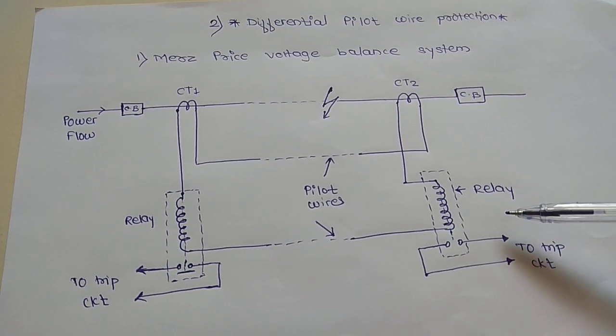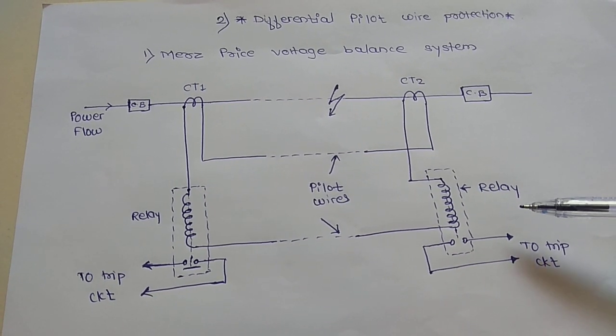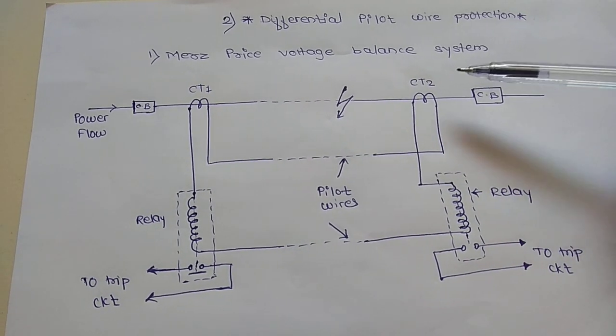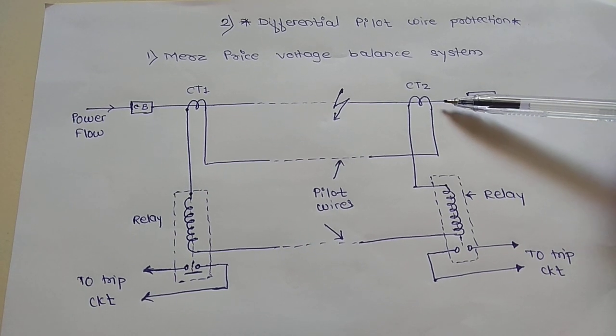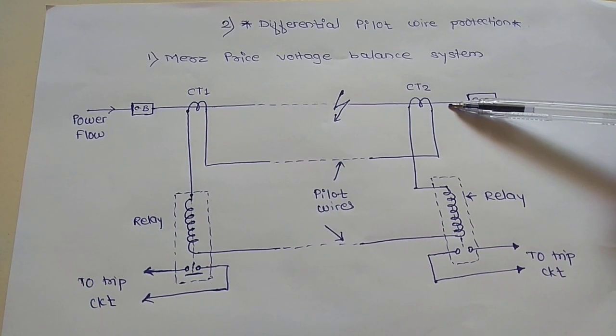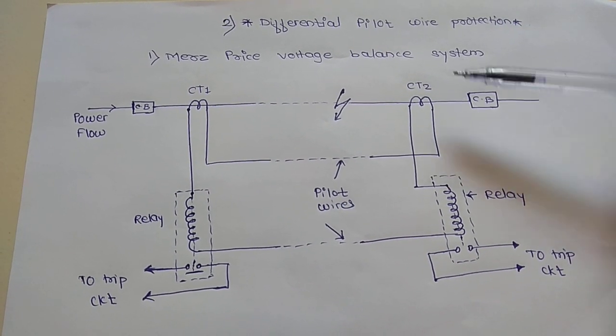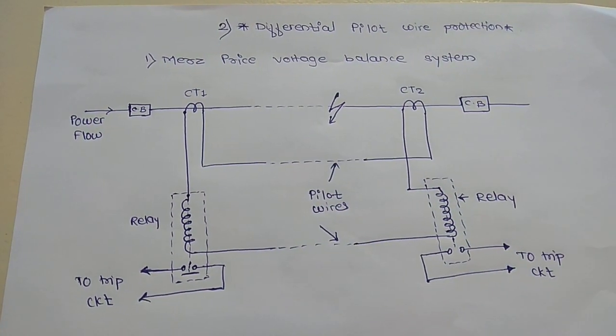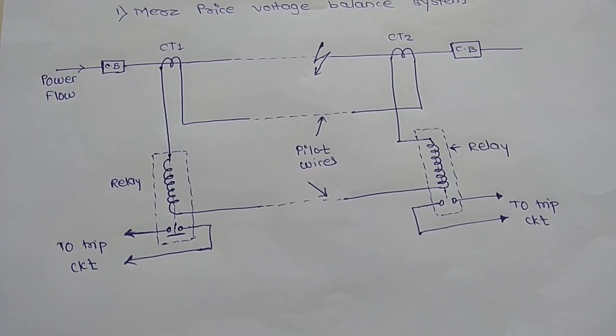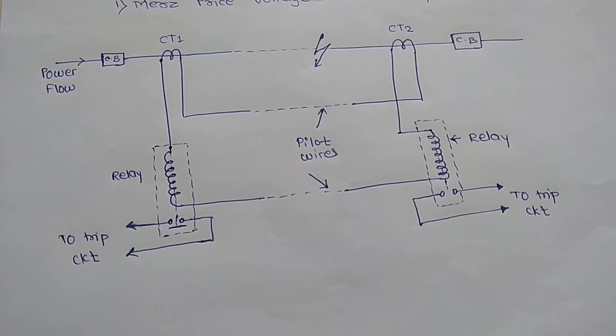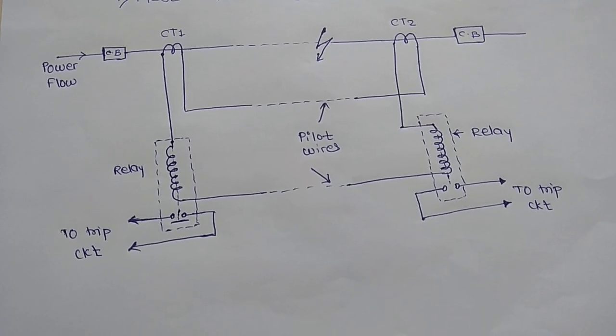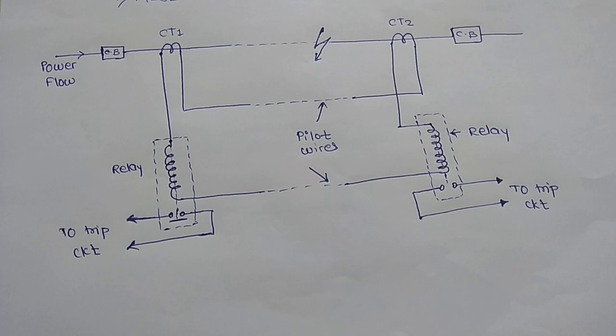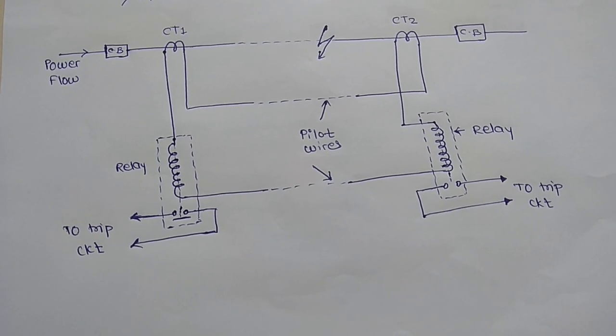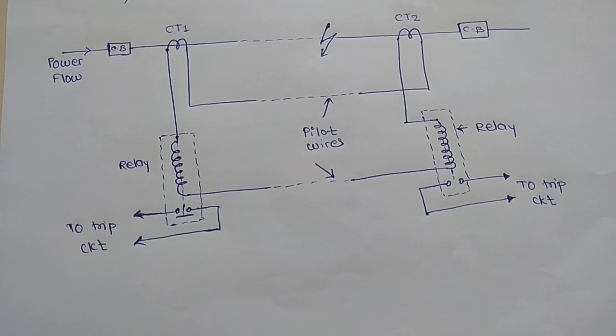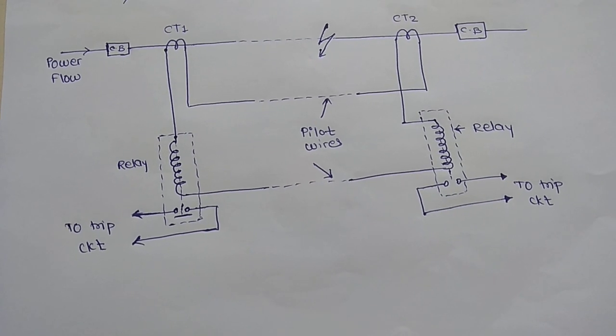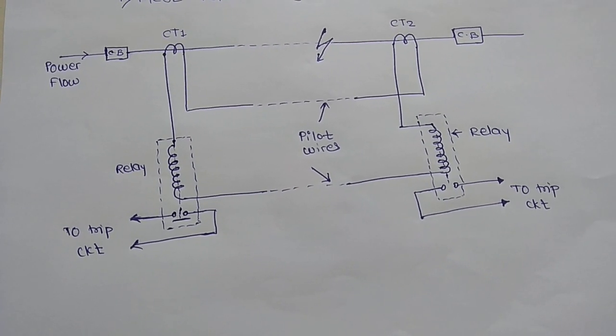This is a schematic diagram for the Merz Price voltage balance system. It consists of a transmission line, and at both ends two CTs are connected, CT1 and CT2. This pair of CTs in each line is connected in series with a relay such that under normal operating condition the secondary voltages are equal and in opposite direction, so they balance each other.